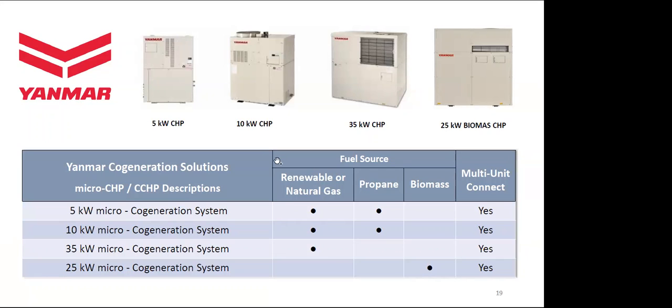Yanmar makes four different units: a 5 kilowatt, a 10 kilowatt, a 25 kilowatt, and a 35 kilowatt. The 5, 10, and 35 all run on renewable gas or natural gas. The 5 and 10, which target remote communities and rural areas, can also run off propane. The 25 kilowatt works off biomass. You can also connect them — for example, take two 10s and make 20 kilowatts, or four 35-kilowatt systems to make 140 kilowatts — because you may have greater loads or varying loads across the seasons.